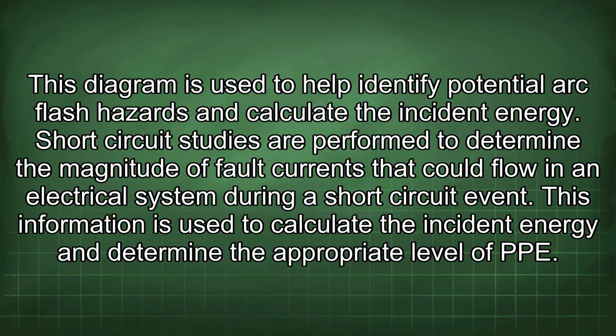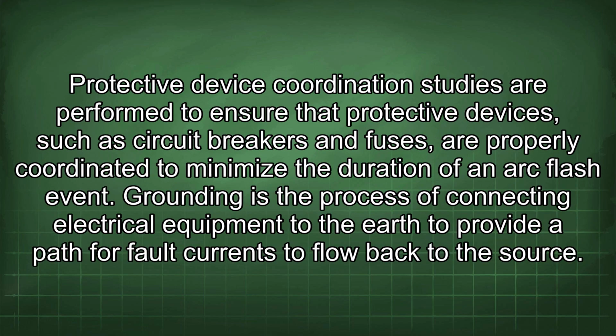Short circuit studies are performed to determine the magnitude of fault currents that could flow in an electrical system during a short circuit event. This information is used to calculate the incident energy and determine the appropriate level of PPE. Protective device coordination studies are performed to ensure that protective devices, such as circuit breakers and fuses, are properly coordinated to minimize the duration of an arc flash event.